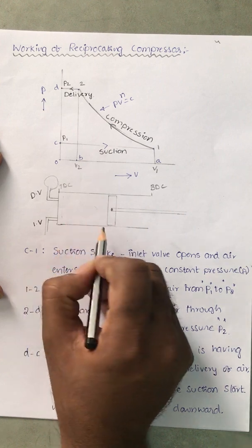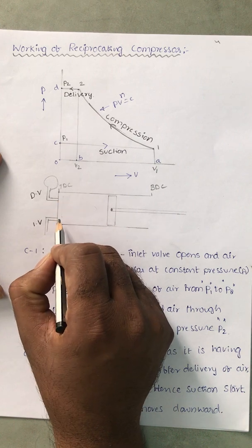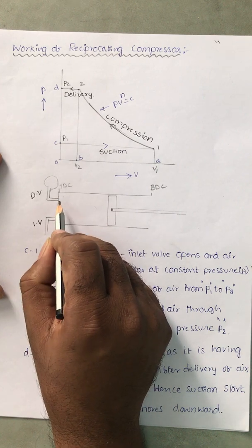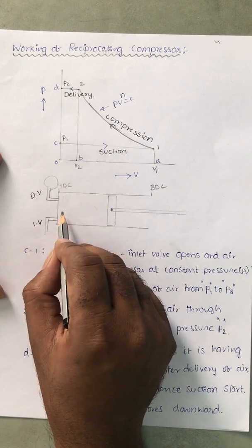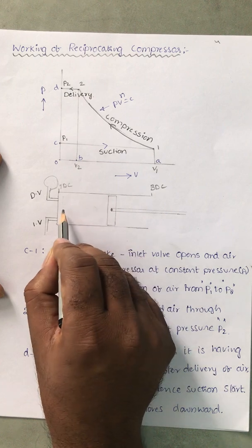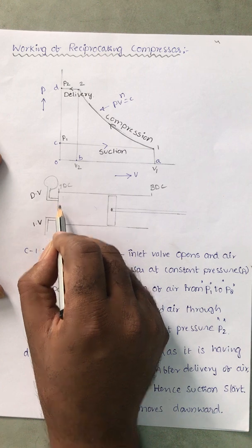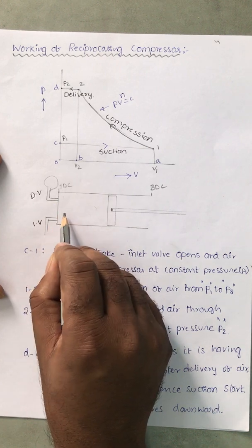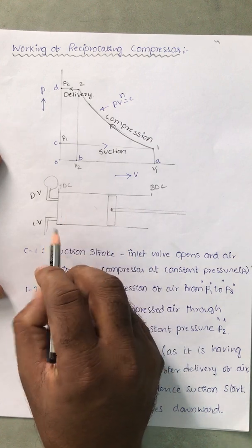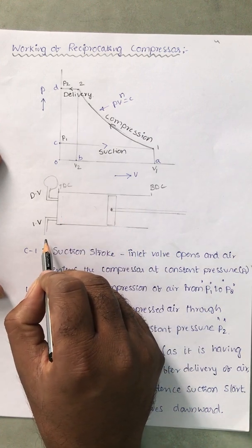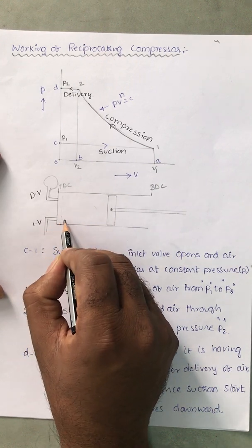This is the piston-cylinder arrangement. When the piston is at the top dead center and starts to move downward, that is called the suction stroke. During the suction stroke, the inlet valve opens and the delivery valve remains closed. As the piston moves downward, a low pressure is created inside, and since the outside air is at atmospheric pressure and inside air is below atmospheric pressure, air enters into the cylinder.